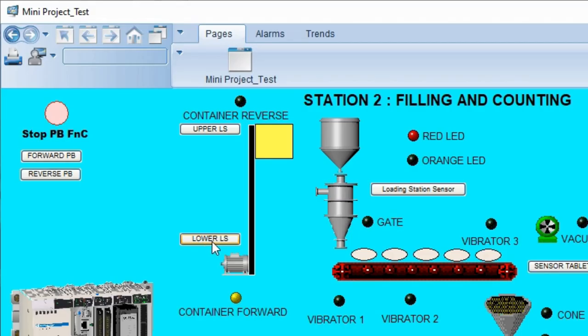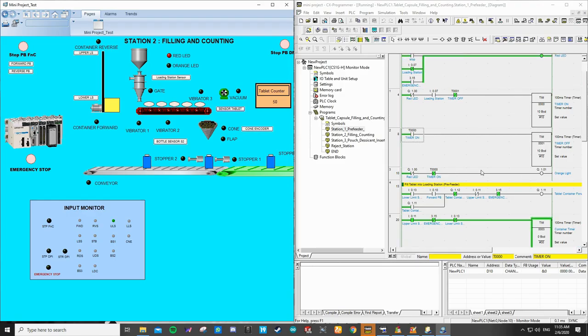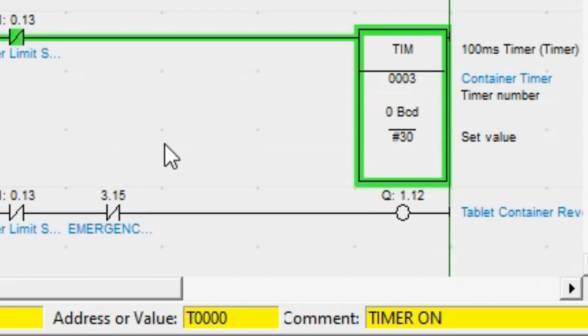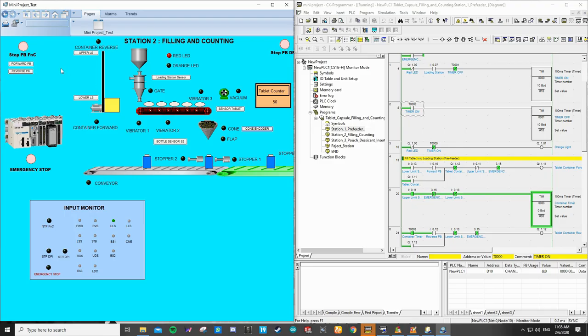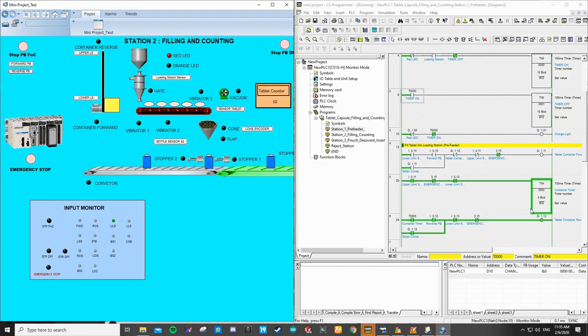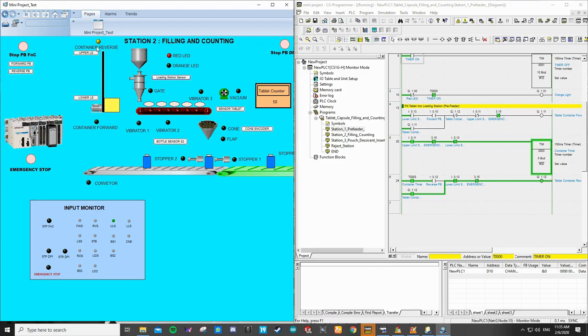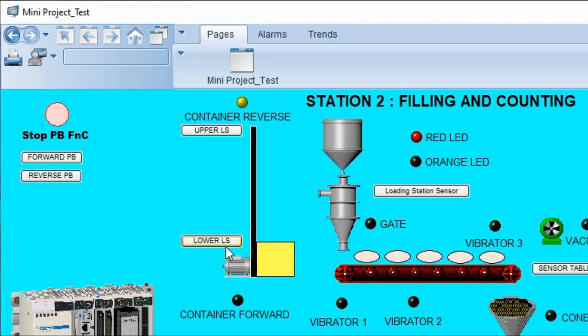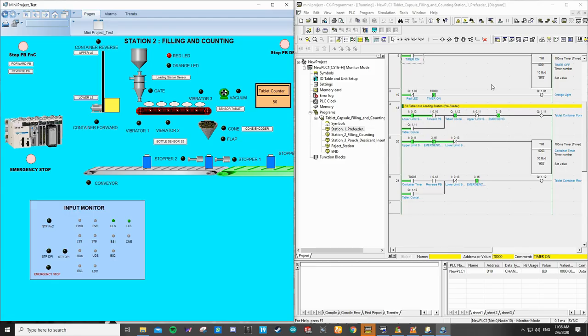And the container forward indicator on the SCADA will be on. After that, the lower limit switch will no longer be contacted — instead, the upper limit switch is hit. When the upper limit switch is hit, the motor will be stopped. All the LED indicators on the SCADA will be off. After waiting 3 seconds, on the CX-Programmer you press the reverse button, and the container will move in reverse — going down and contacting back to the lower limit switch. After it contacts the limit switch, the motor on the Pre-Feeder will be stopped.